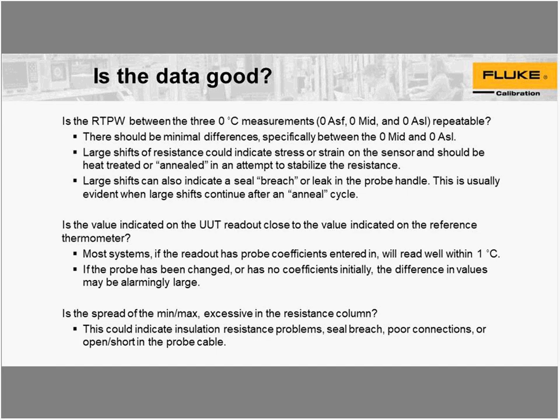Just go ahead and continue recording your data, and we'll calculate new coefficients and load those in and see how it performs after the new coefficients are in. Okay, so the other thing is if the spread of the min-max is excessive, or there is a standard deviation issue, is your probe plain unstable? Okay, it may be fairly repeatable, but it may not fit the limits of stability, uniformity rather.